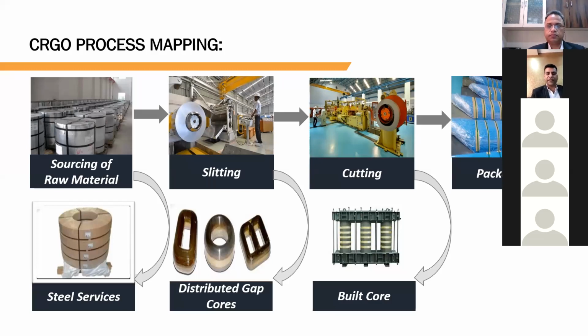After selecting the right grade of CRGO, the next step is slitting. According to the designs of the transformer core, the processor does the slitting process as per the required width of that particular design. The third portion is cutting. Nowadays cutting happens with automatic CNC lines - cutting means cropping of this CRGO slit coil according to the customer design. There are different shapes, which we'll discuss in the next slides, and the CRGO processor cuts those shapes to the required dimensions as per the designs.